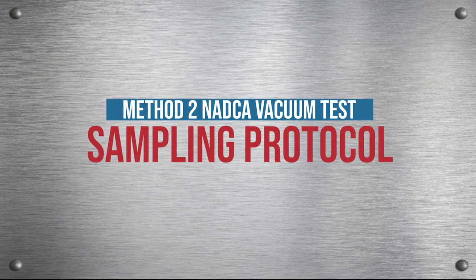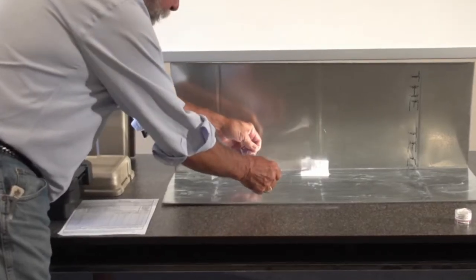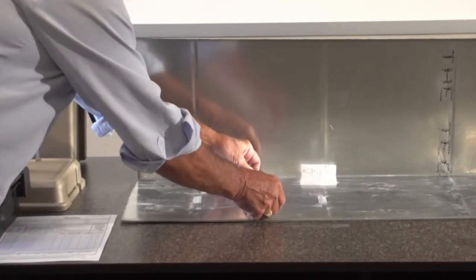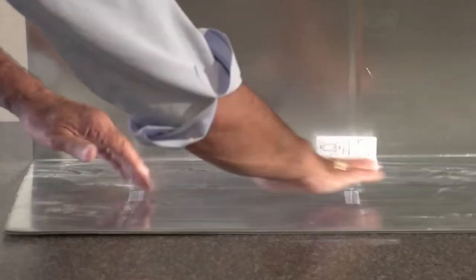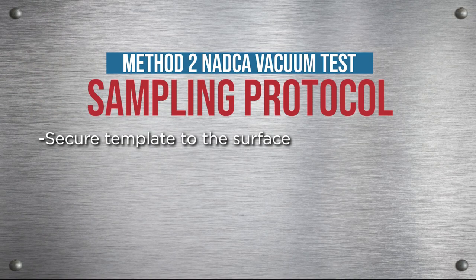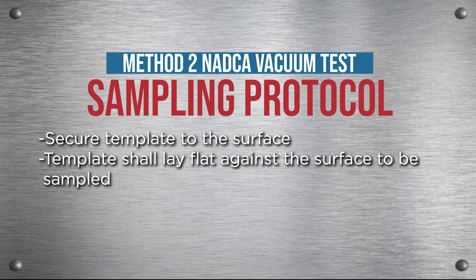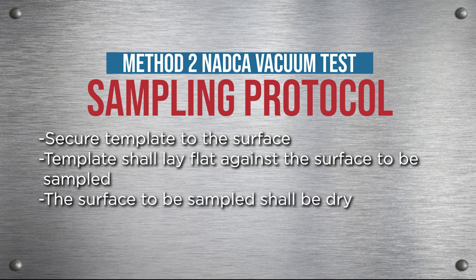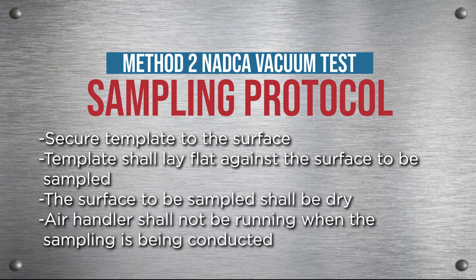Sampling protocol: secure the template to the surface to be sampled so that it will not shift position during sample collection. The template shall lay flat against the surface to be sampled. The surface to be sampled shall be dry. The air handler shall not be running when the sampling is being conducted.